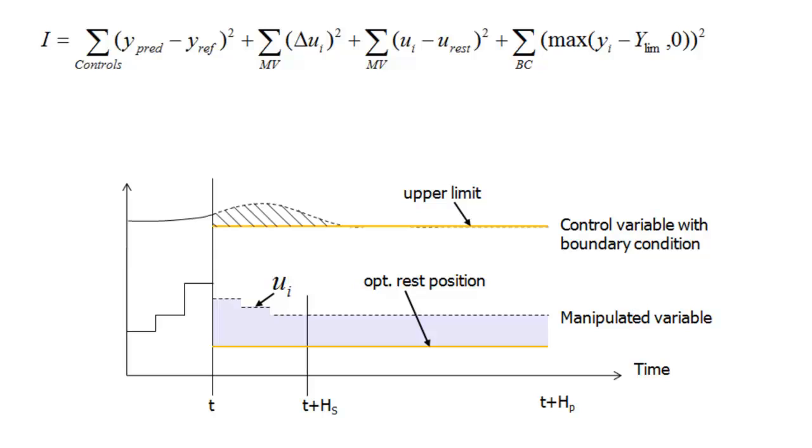Finally, for control variables that have an upper limit instead of a set point, for example NOx and CO, we define the cost as any difference between the variable and the upper limit above zero. In other words, any time the variable exceeds its upper limit, it adds to the cost function. In this manner, the cost function accounts for all the control and manipulated variables in my system.